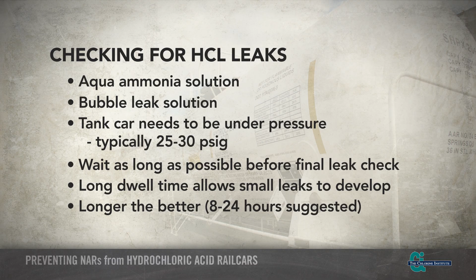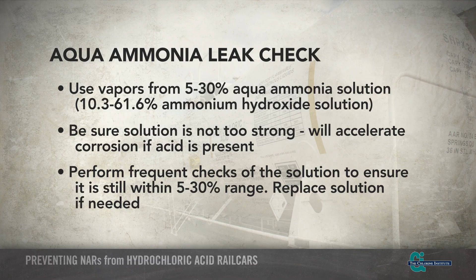If an aqua ammonia solution is used for leak checking, there are some important tips to keep in mind. It is recommended to use a 5 to 30% aqua ammonia solution. Be sure the solution is within this range because a stronger solution can accelerate corrosion if acid is present, and a weaker solution won't be effective in detecting a leak. When using lower concentrations, such as the 5 to 10% range, it is recommended to conduct frequent checks to ensure the solution strength has not degraded below 5%.